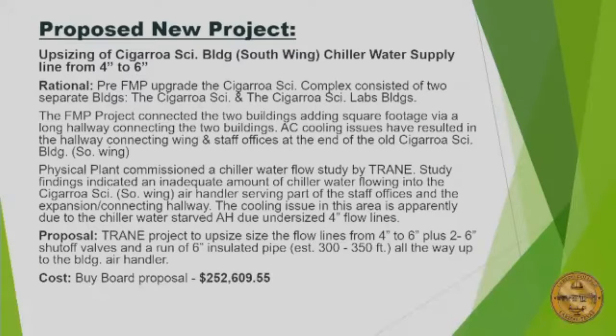The cost difference between 4-inch and 6-inch line is negligible, but with a 4-inch line, buildup forms on the walls of the pipe quickly, reducing the pipe diameter and severely affecting flow. As a result of the flow study, we found there's inadequate chiller water going into the air handler serving that end of the building, so we have a proposal to upsize that line from 4-inch to 6-inch.